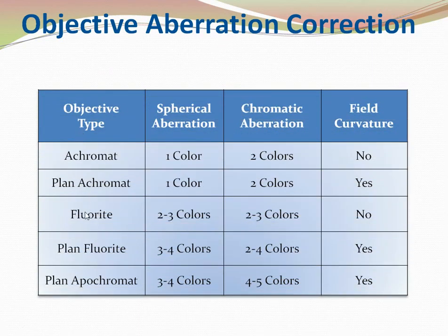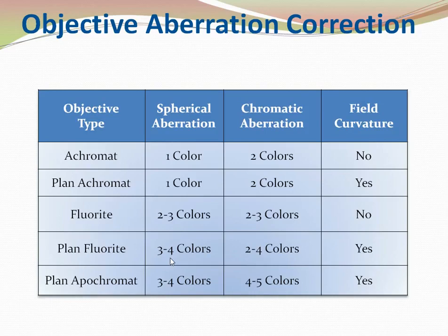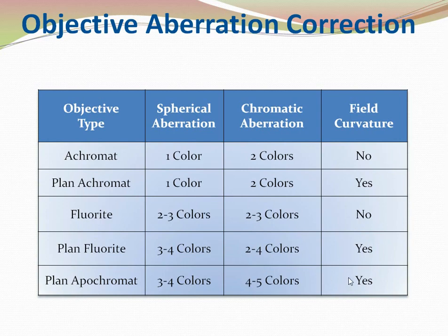These different types of objective lenses are corrected spherically and chromatically, and there is also field curvature correction. If it shows 'plane,' that means it is corrected for field curvature. Plane fluorite is corrected spherically for 3 to 4 colors and chromatically for 2 to 4 colors. The most commonly used objective is the plane apochromate, which is corrected spherically for 3 to 4 wavelengths, chromatically for 4 to 5 colors, and is also fully field-corrected.